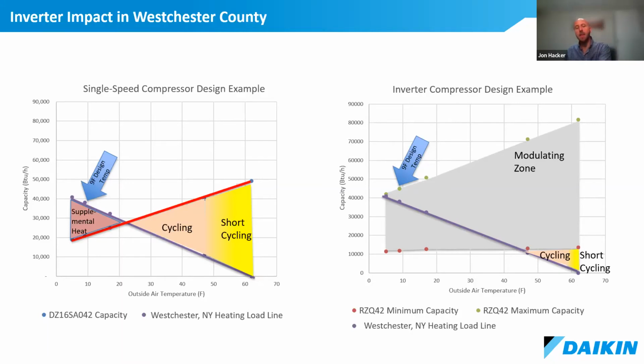And then basically when the heat pump can satisfy comfort, we have cycling. Again, the equipment can't modulate, it can only turn on and off. So we've got what I'd suggest is healthy cycling until around maybe 48 degrees Fahrenheit. But then at that point, the ratio of heating needed to maintain comfort, which is the purple line, to the capacity of the equipment in red, there's a big order of magnitude difference there around 47, 48 F, right? That equipment can provide 4 times as much heat as what's actually needed. So when it's just below 50 degrees outside, that equipment will operate about 1/4 of the time per hour, right? So maybe 15 minutes out of every hour, but it may operate for 5 minutes 3 times over an hour, right? And that's short cycling, and that's a very inefficient way to operate the equipment.